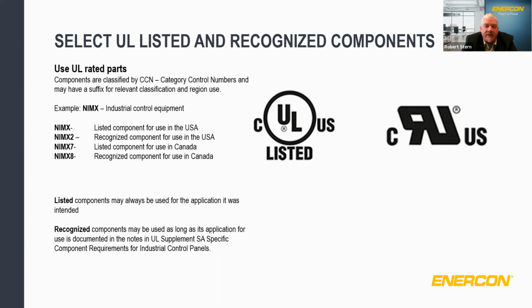Now, what's the difference between these two? Well, a listed UL component may always be used in the application that it was intended for. So for example, if it was a branch circuit breaker, it could always be used in that application. If it's a recognized component, the component may be used as long as its application for use is documented in what's considered the UL supplement SA, specific component requirements for industrial control panels. So there's a prescribed use that says this component under this CCN with this particular coding may be used in this application. Go on, next page, please.